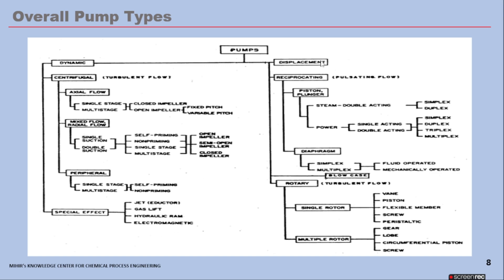On the right you have the positive displacement pump, where you have the reciprocating types: piston/plunger and diaphragm. Then blow case and rotary. A blow case is essentially a pressure vessel in which you pressurize, close the pressure, transfer the liquid under pressure, then when the pressure drops you close the transfer, pressurize again — so it's a blow case basically.